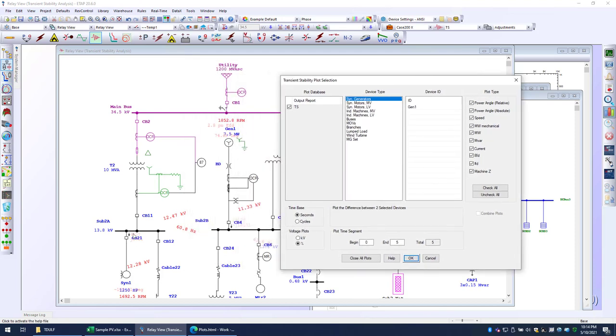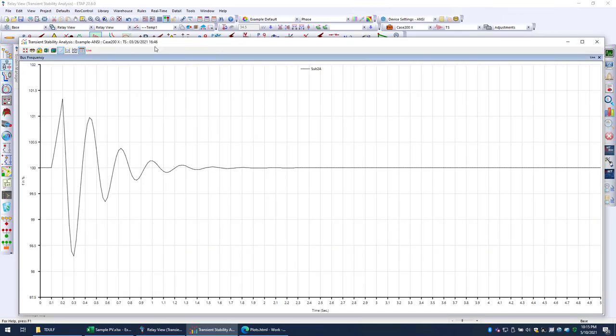So I will take a look at sub-2A because this synchronous motor here is actually critical. I want to see if my load shedding would actually activate. So I'm going to head over to bus sub-2A. I want to look at my frequency. And here you can see that it does not go above the 2% that I have the frequency relay set to. So there's definitely that damping effect. You can see how the frequency reacts, but it's not sufficient to trigger my 2% load shedding setting for this particular relay.